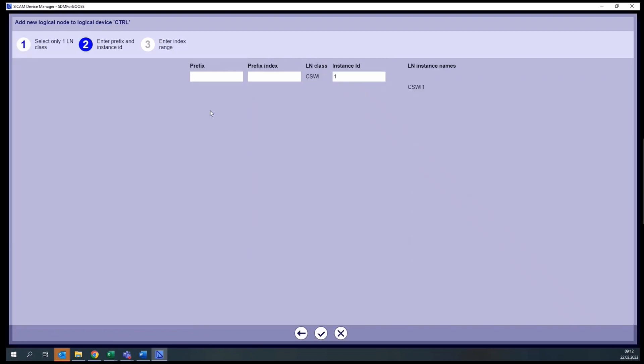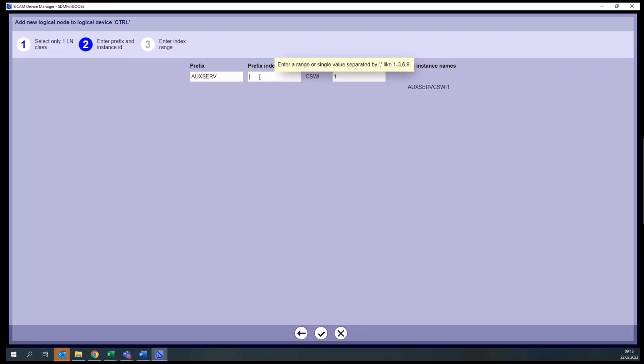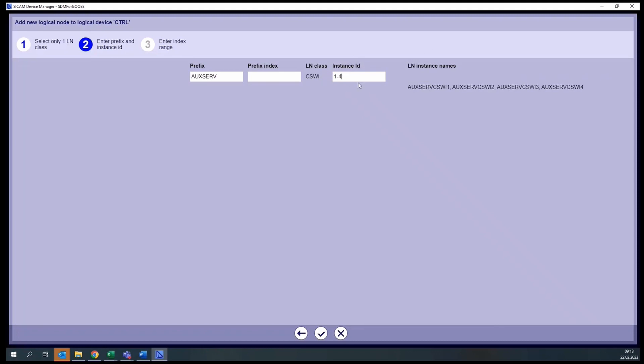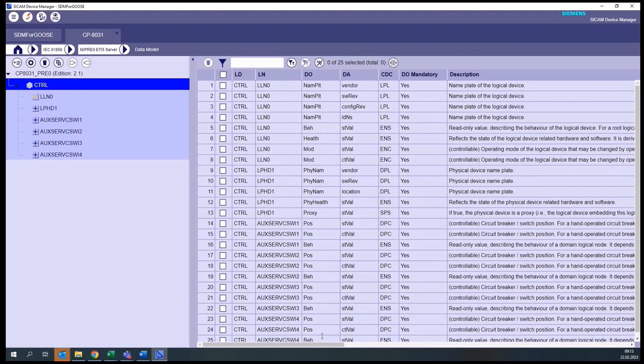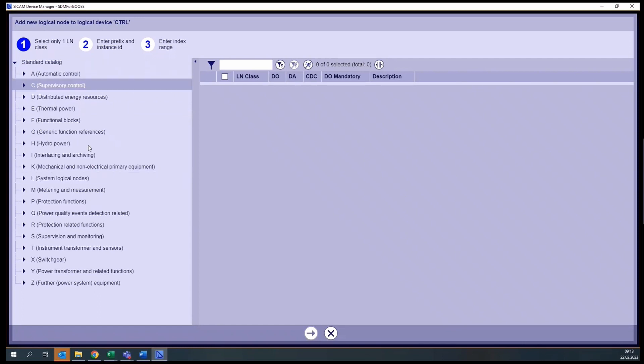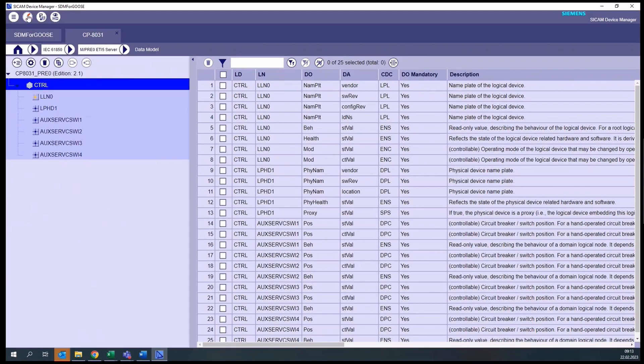Now we can type in a prefix and an index. In this example, let's create the prefix 'auxserv', as if it were for switching devices used for auxiliary services. We can also define an index, as if we had several groups of auxiliary services. But if this is our only group with this prefix, we can leave this field empty. Finally, we define how many switching devices we want within this group — we chose four switchgears, so we choose instance ID 1 to 4. Then we confirm and the logical nodes are automatically created on the left side. In the same way, you could create general information, inputs, outputs, or measurements, and so on. It's just a matter of having some knowledge of the standard IEC 61850 logical nodes available, and based on this we can create a very complex data model.